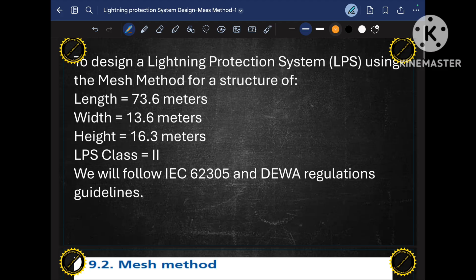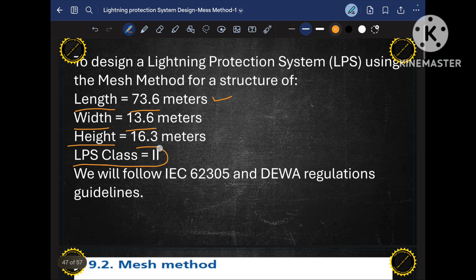As you remember, when we discussed the rolling sphere method we took an example for our worker accommodation, which has dimensions: length 73.6 meters, width 13.6 meters, and height 16.3 meters. In part 2 or part 3 video I discussed how to select the class for a particular project. Based on that we concluded that our project requires LPS class 2. So we will take the same example but change the method from rolling sphere to MESH method.